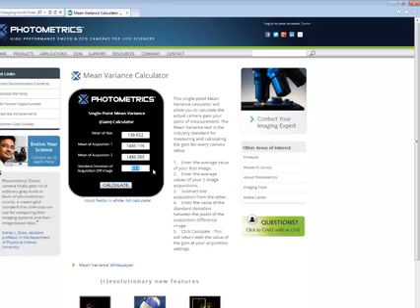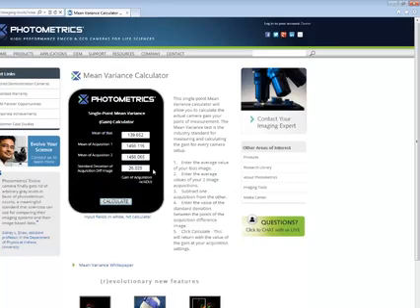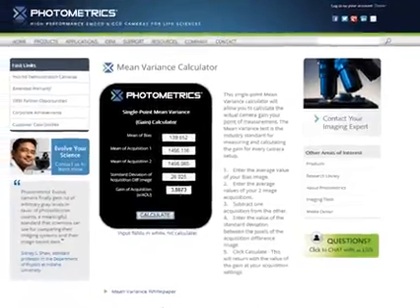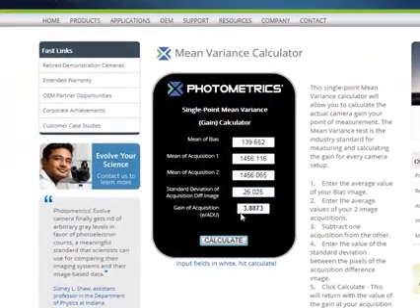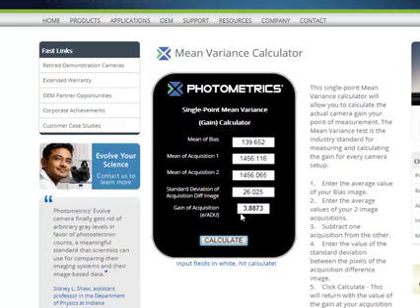Let's plug that in: 26.025. That tells me now that this camera is converting 3.8 electrons for every grayscale on the screen, which is pretty standard for a 12-bit camera.